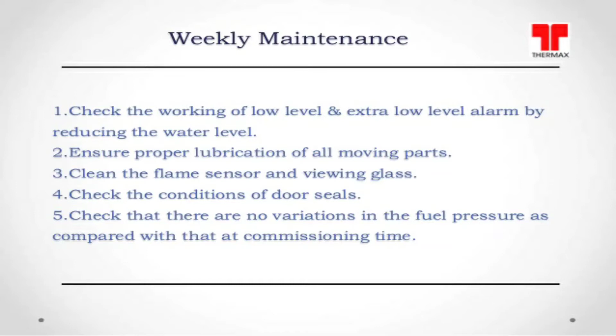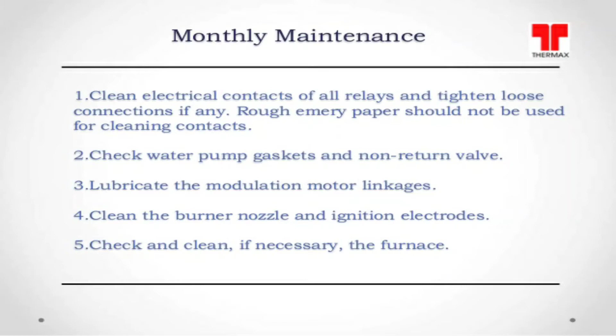Then monthly maintenance. First of all, clean electrical contacts of all relays and tighten loose connections if any. Rough emery paper should not be used for cleaning contacts. Second, check water pump, gaskets and non-return valve. Third, lubricate the modulation motor linkages. Fourth, clean the burner, nozzle and ignition electrodes. Fifth, check and clean if necessary the furnace.